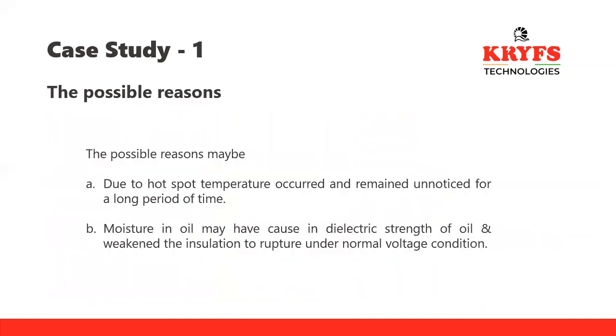We did the root cause analysis, rectified the problem of the transformer, and found the possible reason for the failure. It is basically due to the hotspot temperature, because a short circuit occurred, a puncture within the insulation of the transformer. The hotspot temperature persisted for a longer period of time, and the moisture in the oil may have reduced the dielectric strength of the oil and weakened the insulation of the winding, and it leads to rupture of the winding insulation even under normal voltage condition.